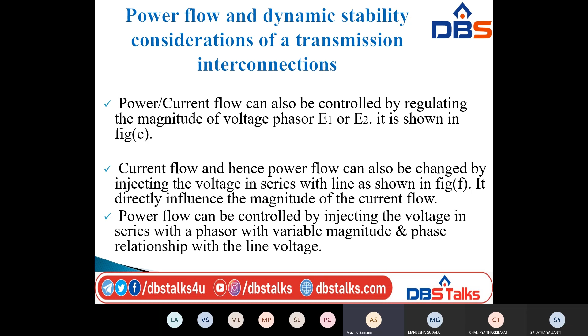Here power or current flow can also be controlled by regulating the magnitude of voltage phasors E1 and E2, as shown in figure E. By using this diagram, that means E1 and E2, we control the power and current flow. This also means that regulation of the magnitude of the voltage phasors E1 and E2 has much more influence over the reactive power flow than the active power flow.